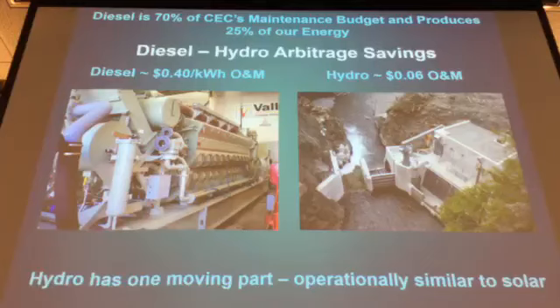Even if they ran perfectly, every 30,000 hours, depending on the size of the generator, you're into a rebuild costing $300,000 to $750,000, or $300,000 to about $500,000. That's $10 to $15 an hour just for rebuild cost, and this also leaves out other costs like lube oil.